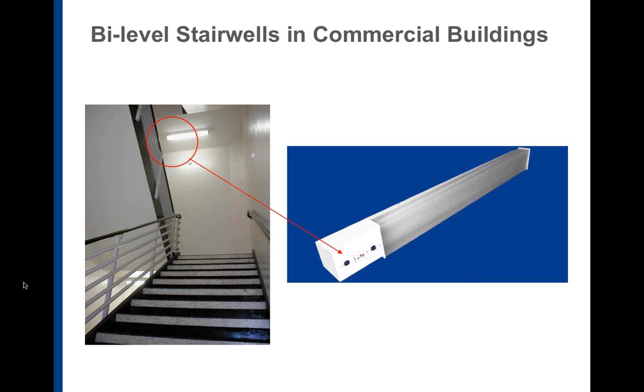So let's look at stairwells. For CLTC, we consider this an early win. We also consider it a proven strategy. Stairwells are often overlooked as places where lighting is on 24/7, regardless of occupancy. And through our work over the last 5 to 7 years, we are now aware of at least 5 manufacturing companies that make excellent products with integrated sensing that you can use in stairwells, and you can also combine basic stairwell lighting with controls, not necessarily using an integrated unit, to achieve the same results. Next slide.